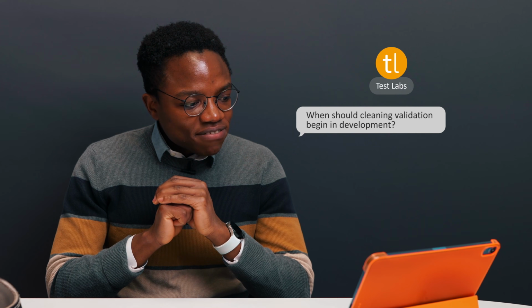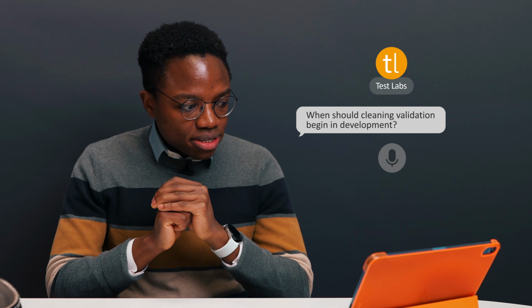When should cleaning validation begin in development? So when you start generating evidence for your claims, it's probably around when you're just about ready for submission. The key point is that the medical devices you're generating evidence on are in the state that you would, for example, ship them to your end users. As long as the evidence is generated on the final design of your medical devices, everything's going to be fine.